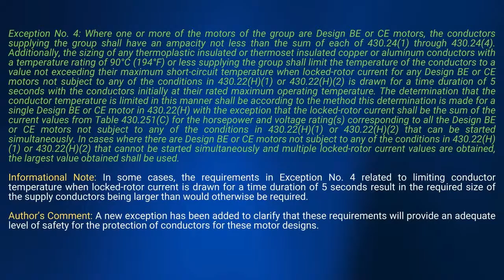Now, the other one gets into the disconnecting means, where you have circuits over 1,000 volts AC, 1,500 volts DC. Remember, they've moved a lot of stuff around when dealing with high voltage, giving it its own parts. They haven't done this in motors yet, but I expect it to eventually happen. Right now they just get into the disconnecting means where you're over 1,000 volts, and they talk about your motor controller disconnecting means, telling you it has to comply with 430.102 and shall be lockable in accordance with 110.25.